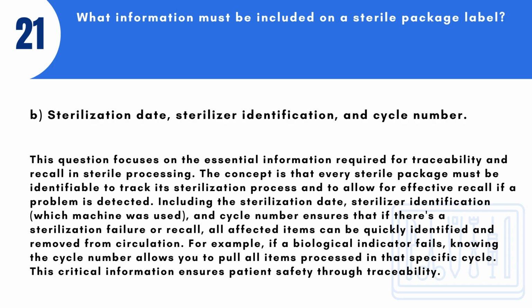Including the sterilization date, sterilizer identification, which machine was used, and cycle number ensures that if there's a sterilization failure or recall, all affected items can be quickly identified and removed from circulation. For example, if a biological indicator fails, knowing the cycle number allows you to pull all items processed in that specific cycle. This critical information ensures patient safety through traceability.